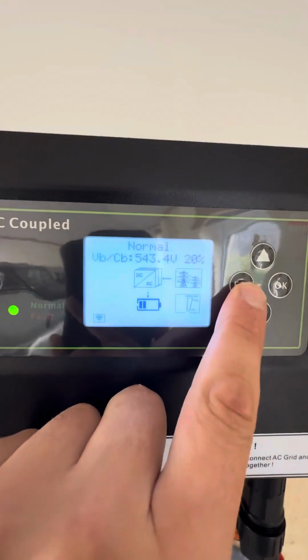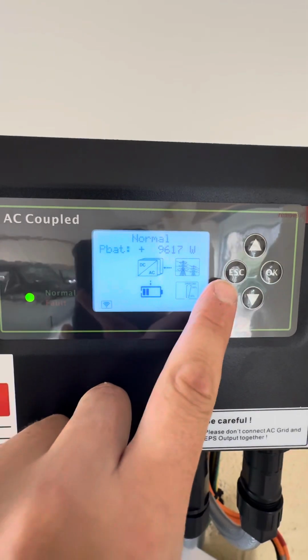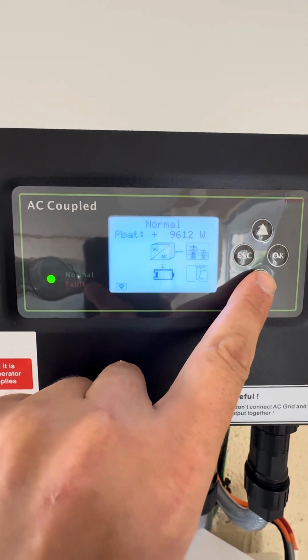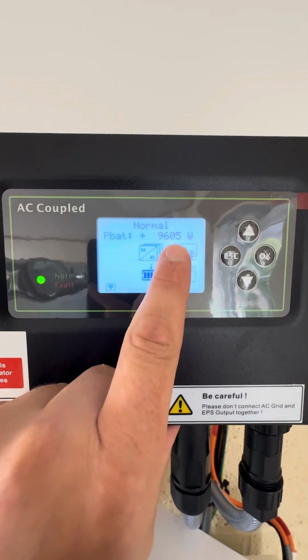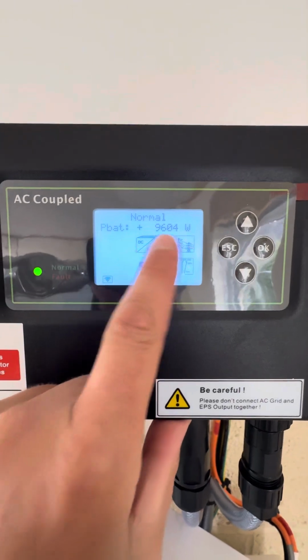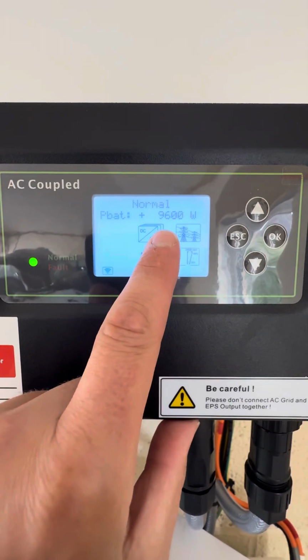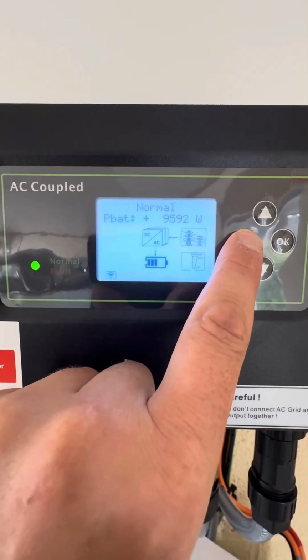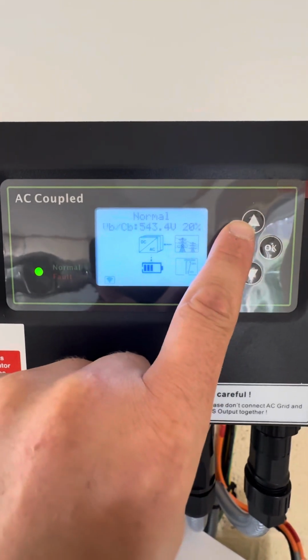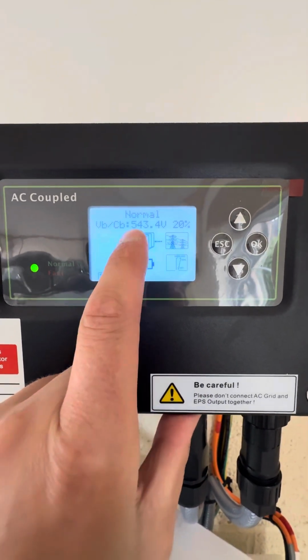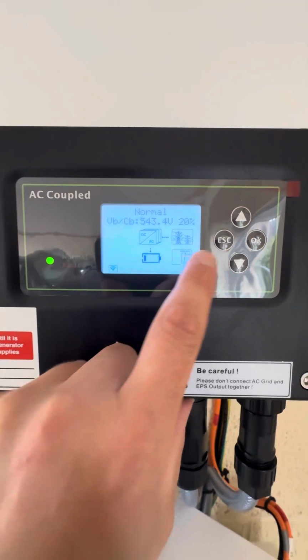It's got the ability to charge and discharge the batteries up to 10 kilowatts per hour. It's a high voltage battery system, with one BMS controlling up to 10 batteries, which you can then parallel up. As it stands, it's putting 9,600 watts into the batteries, with the battery charge at 20% and 543 volts at the moment.